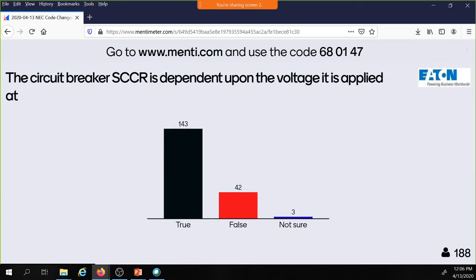This one really upsets me because I know we went through this. Circuit breaker's short circuit current rating is dependent upon the voltage it is applied at. I know it's a poorly written sentence. I shouldn't end it in the word at, but circuit breakers do not have a short circuit current rating. Circuit breakers have an interrupting rating. So the answer to this one should have been false. U46, I love you.